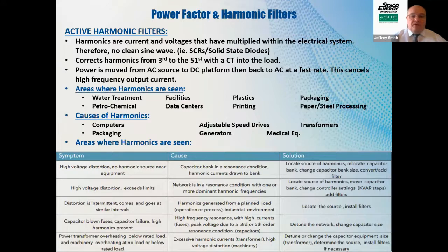So, power factor and harmonic filters. Harmonic filters are, I guess what I try to tell people, just think about the noise cancellation headphones that you wear. What they do is they take the sound that's out there, put it in there, do a 180-degree phase shift and send it back out there. Basically, the harmonic filter does the same thing. We read the harmonics that are on the line right where we're looking at, and then we inject a 180-degree signal into that system to eliminate the harmonics. We go from basically the 3rd to the 51st harmonic in these types of systems.